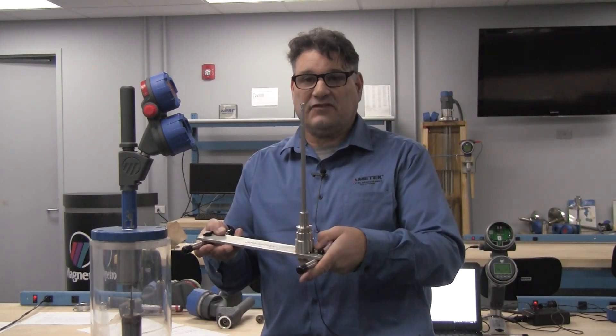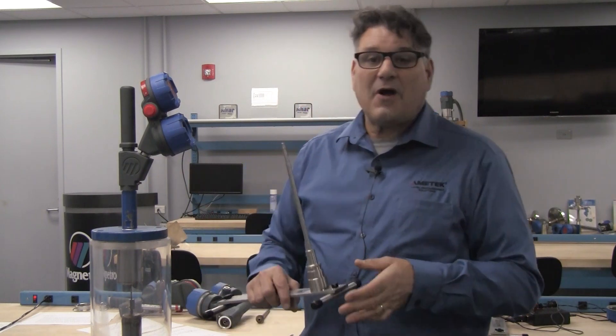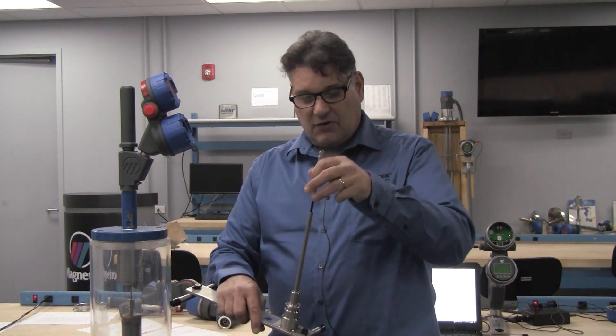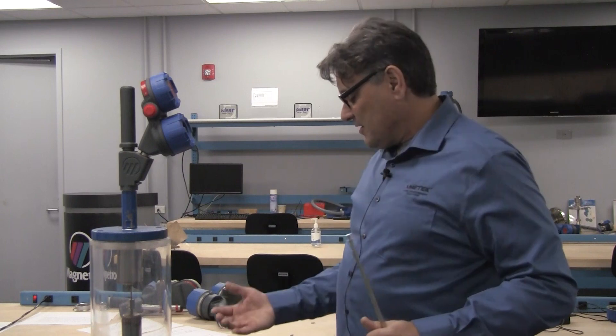We'll be performing our installation on a demo calibration stand, but a similar process can be performed whether using weights in an instrument shop or if changing levels in the process. This demo stand will simply allow me to move the core stem as if there is physical level movement on a displacer.